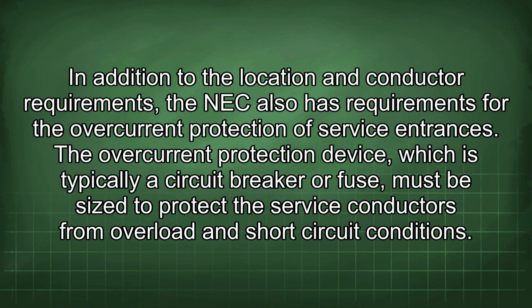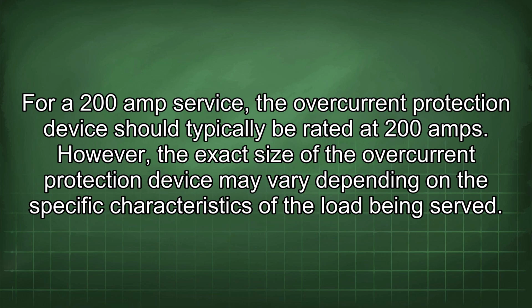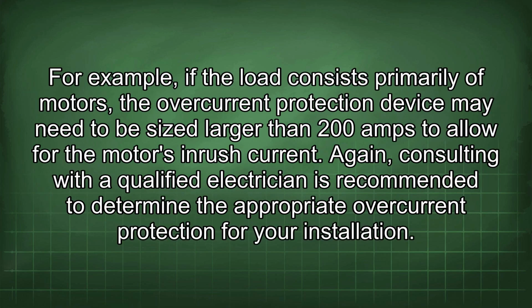In addition to the location and conductor requirements, the NEC also has requirements for the overcurrent protection of service entrances. The overcurrent protection device, which is typically a circuit breaker or fuse, must be sized to protect the service conductors from overload and short-circuit conditions. For a 200 amp service, the overcurrent protection device should typically be rated at 200 amps. However, the exact size of the overcurrent protection device may vary depending on the specific characteristics of the load being served. For example, if the load consists primarily of motors, the overcurrent protection device may need to be sized larger than 200 amps to allow for the motor's inrush current.